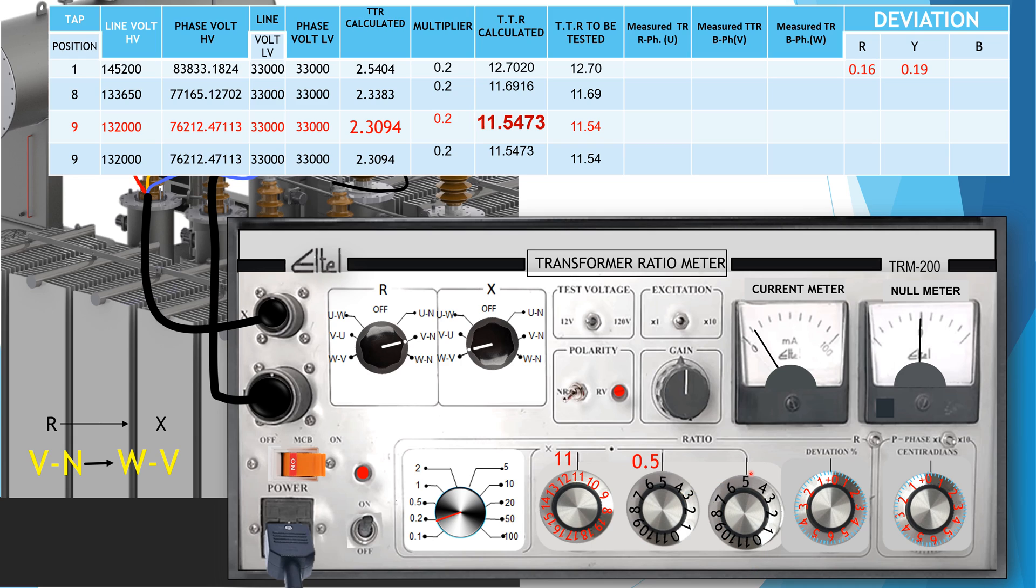Measured TTR of B-phase at tap position 9 is 11.55, that is 2.3105.